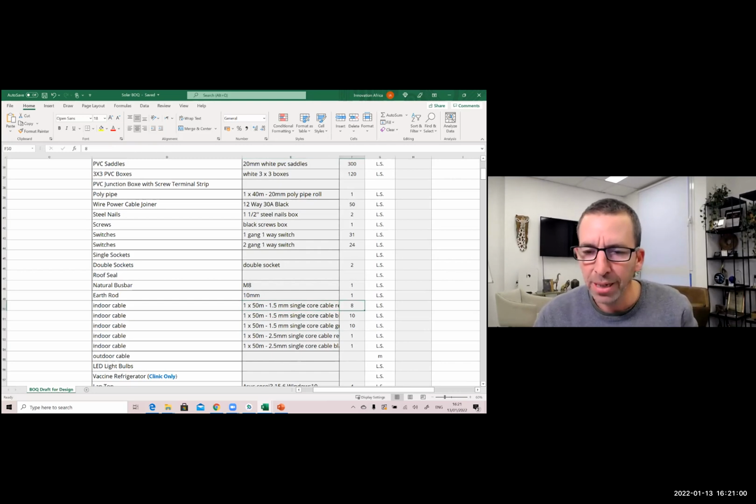So if the contractor put 8 in the BOQ, it should fit the design, meaning that when you did the design, you saw that this is the amount of wiring needed. By the way, if it's more, it's also okay. It's no problem if he puts a bit more. We don't want to be always over the edge.